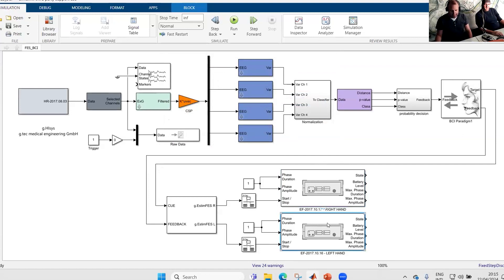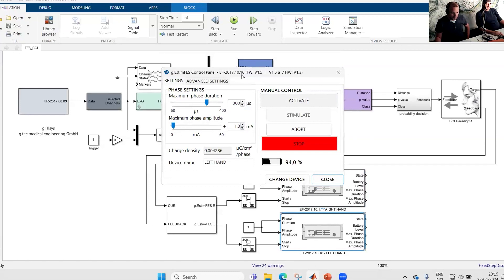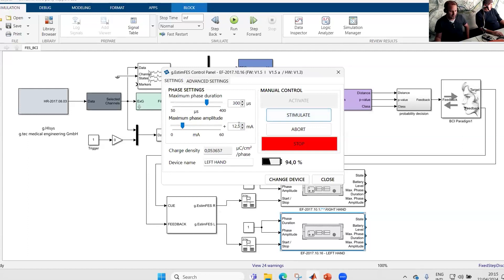We do the same for the second side — the left hand. The stimulator is doing a self-test again. There is a buzz feedback from the device, which you hear when it's stimulating or doing the self-test. Let's increase directly a bit. You feel it? Here we actually directly got the right position — you can see on the left-hand side, just the movement. That's what we want to have.